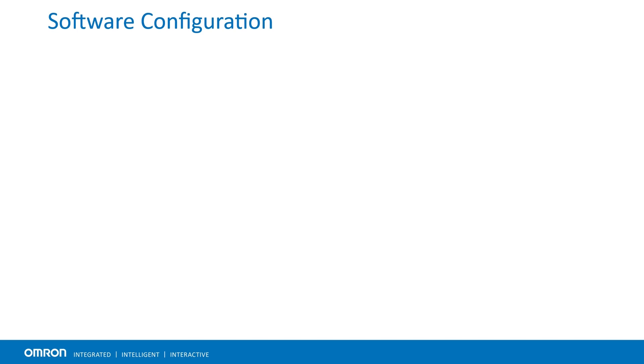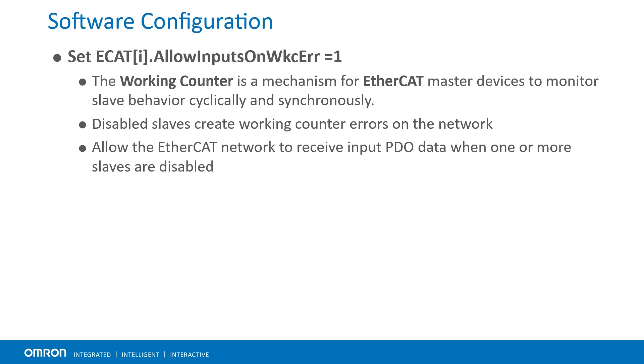On the software side, you will have to set a few parameters to the standard EtherCAT configuration before you disable any slave and activate the master. First, set ECAT[0].AllowInputsOnWCError to 1. The working counter is a mechanism for EtherCAT master devices to monitor slave behavior in case of invalid or inconsistent data. When devices are disabled from the network, it creates a working counter error and prevents PDO communication. Setting this parameter allows PMAC to receive PDO data when one or more slaves are disabled.